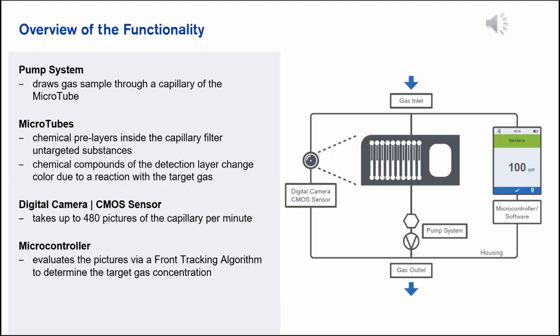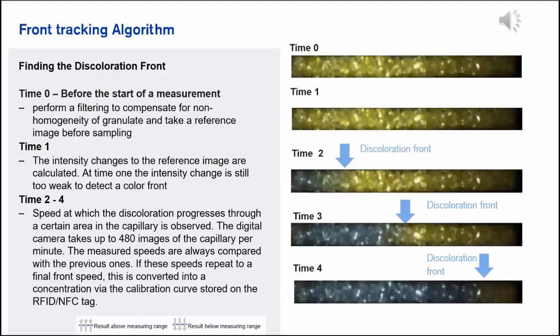So what is a CMOS sensor? Well, CMOS is an acronym for a complementary metal oxide semiconductor. And basically, in layman's terms, what it is is a means to convert light into electrical signals which we then use to give a simple digital display in the readout. So what is a CMOS sensor at the end of the day? It's basically that technology that we have in all of our smartphones that give us those high-resolution digital images that we like to share with our family and our friends. So it's that sort of technology that Dräger have designed into this system.